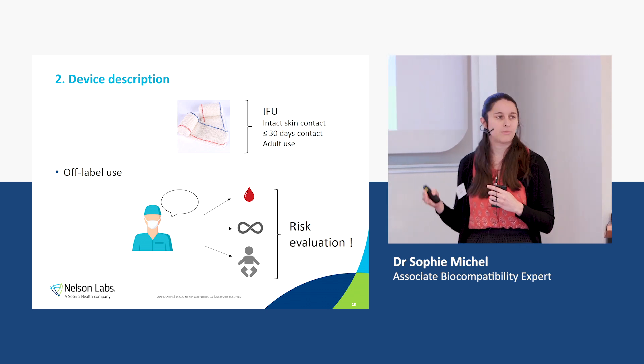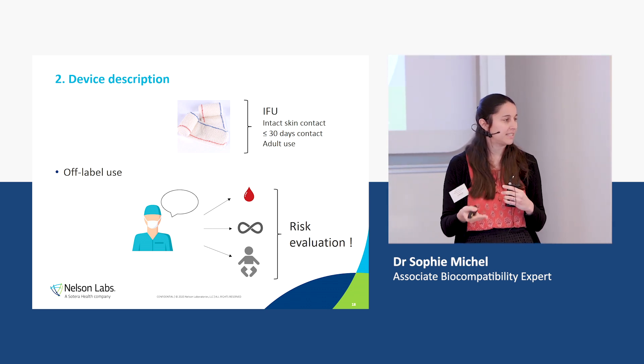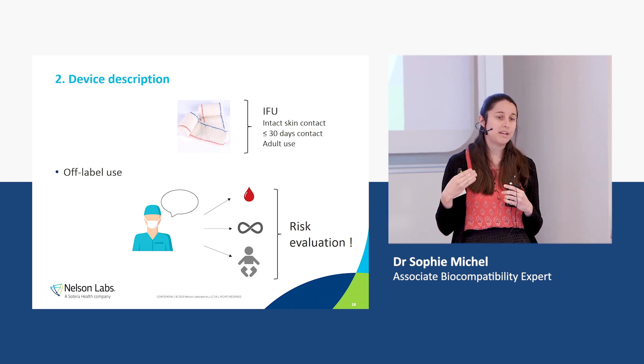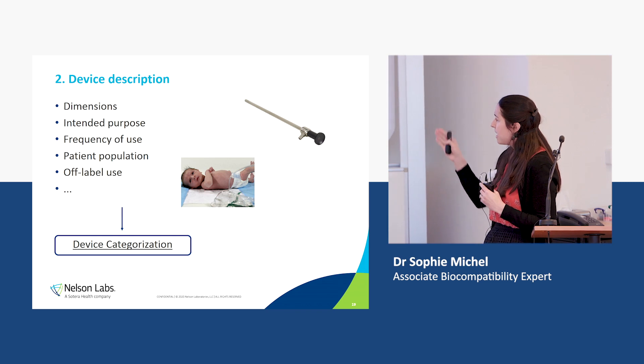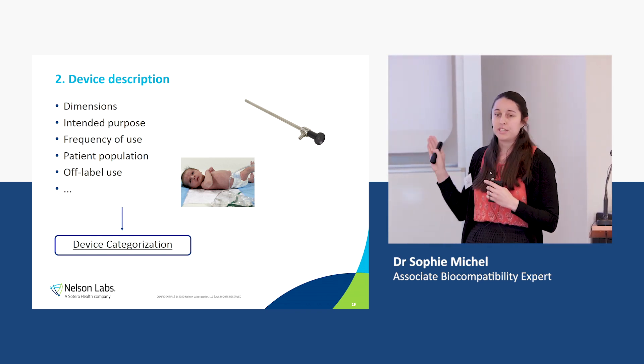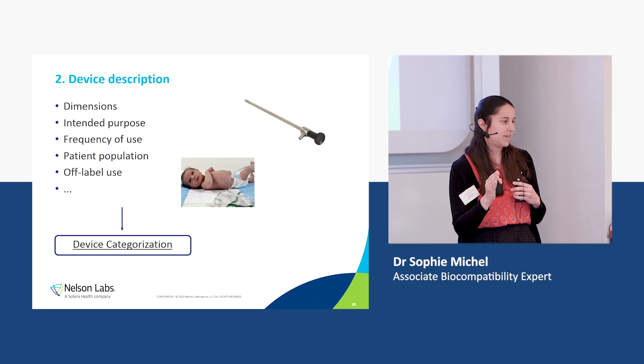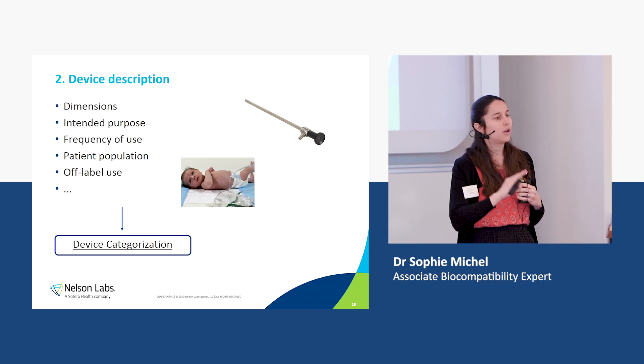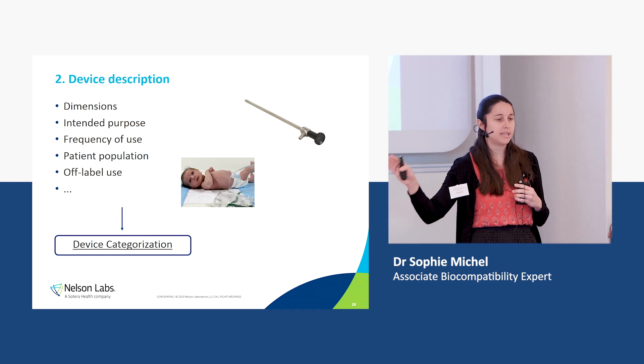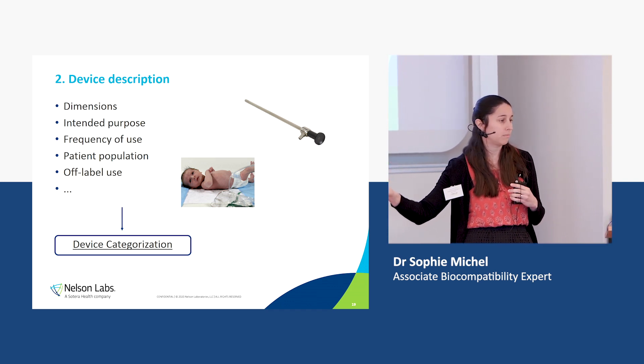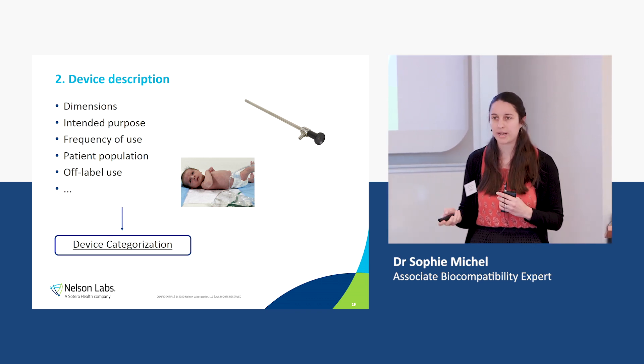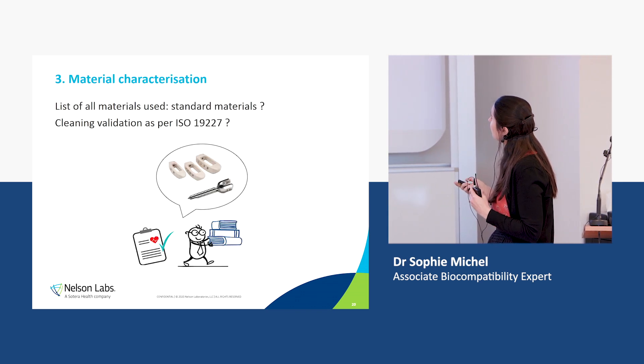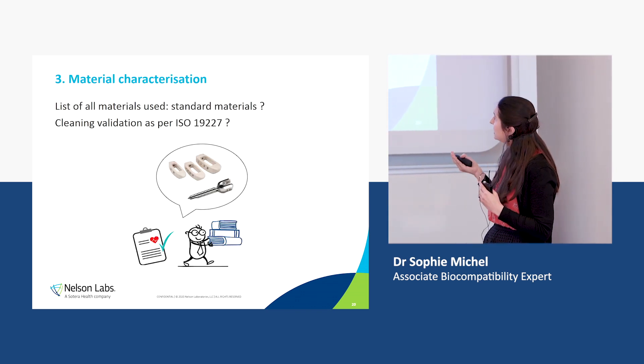All this aims at having a good device categorization. If you make a wrong device categorization, in 90% of cases your risks are not going to be well addressed, your testing in phase two will also not be well addressed, and your conclusion in phase three on patient safety will also not be correct. Then we want to do material characterization — we want to understand every material used in your medical device. Is it a standard material like polyethylene, polypropylene, or stainless steel? Then maybe we can use some data from literature or from previous medical devices.